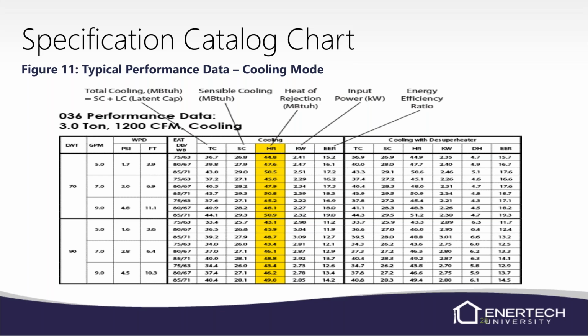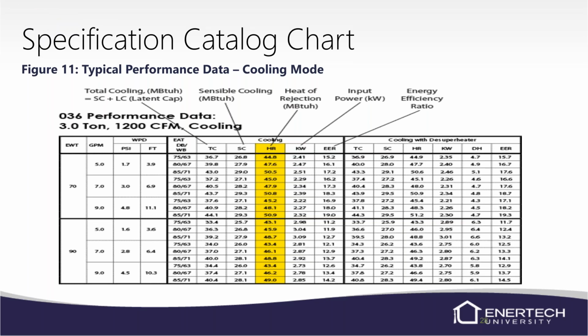On the cooling side of things, now we look at total cooling capacity, our sensible cooling, and our heat of rejection. If you ever looked or thought about it, you'll see that heat of extraction is always lower than your heat of rejection. And that's not because the units can't perform as well. The heat of rejection includes your heat of compression. We still have that heat in cooling mode that we have to pick up and do something with. So we're picking it up and putting it into the loop field instead of picking it up and putting it into the home, which is counterintuitive because we're trying to cool the home.